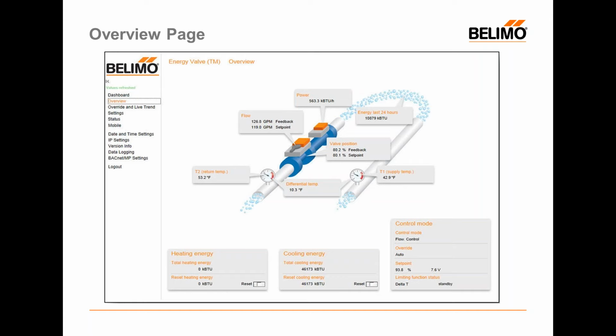When you first tie into the Belimo Energy Valve's web server, you're going to see a couple of web pages that look like this. The first one you'll come to is the dashboard, which basically shows the upper portion of the screen we're looking at here. So the image of the valve, the entering and leaving pipes with the temperature sensors. You'll see valve position, flow, calculated power, and the power can be calculated or selected for watts, kW, BTUs per hour, kBTUs per hour, or even tons. Calculated differential temp, flow, valve position.